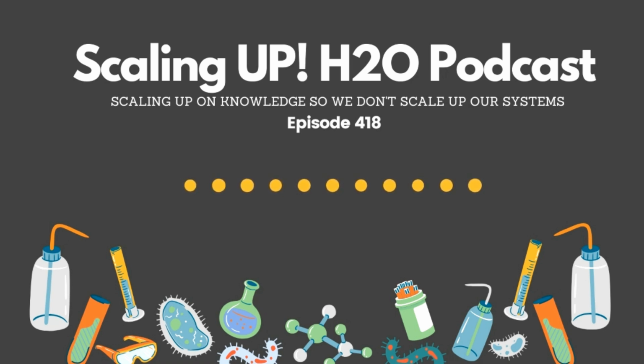Now, all that being said, in fairness to HPA, it has been used for decades quite successfully. You can debate whether that is a combination of HPA functioning as a corrosion inhibitor and/or orthophosphate that's a decomposition product or an oxidation product from it. That's probably something people could talk through. But what's not particularly debatable is HPA has been delivering good corrosion rates for mild steel for decades. So, what is a new maleic-based corrosion inhibitor?